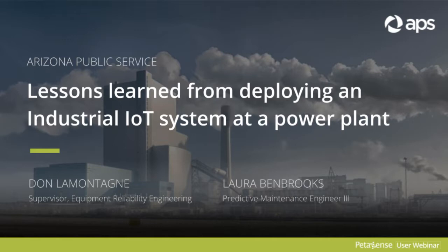All right, so we have one question here for Don. Don, are you monitoring any equipment internal to the units? Any interference issues there? That's one of the sensors we still have to try out. We have a lube oil pump inside the turbine enclosure, very close to the generator obviously, so we want to try that out with just the sensor alone and see if the signal comes back out of the enclosure. If not, that's what we talked about with transmitters earlier - we may try a transmitter on the outside of the enclosure and see what kind of signal we get that way. So we're going to try a plan A, plan B on that and see how it works.